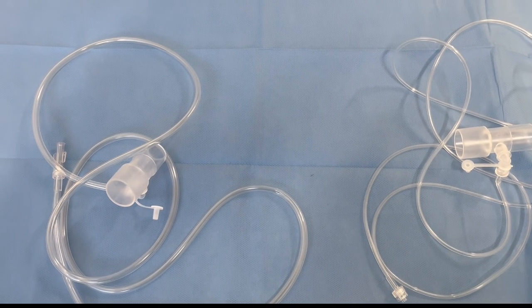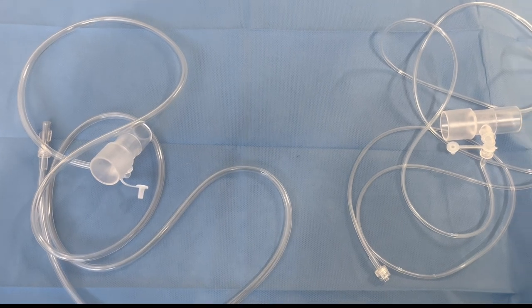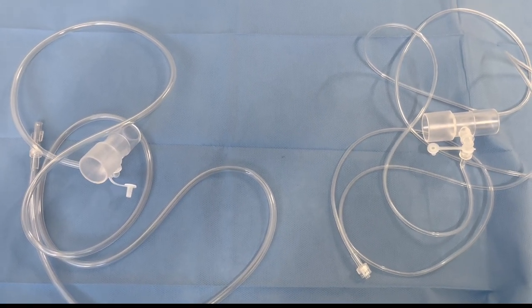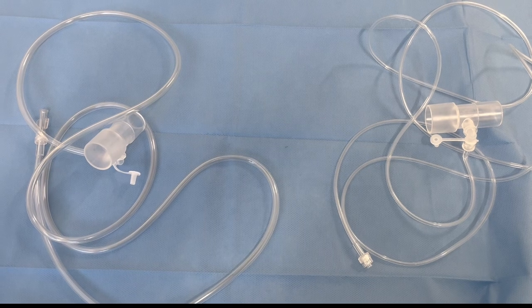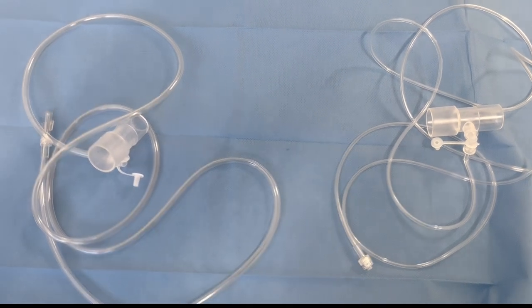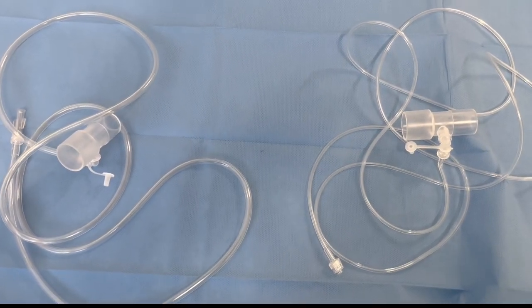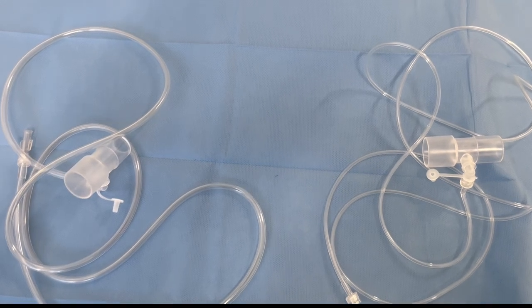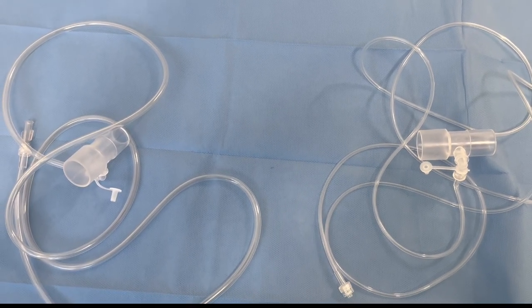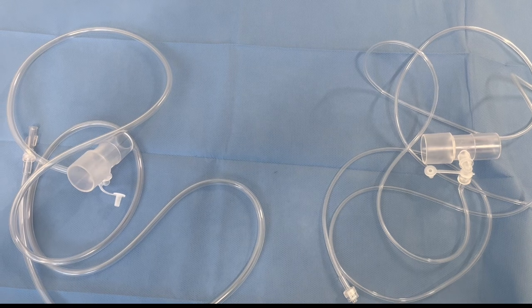Before we use the machine, we should familiarise ourselves with the disposables. One potential problem that has been identified early is the identical nature of the nitric injection adapter and the sample line adapter. This could lead to the sample line being connected onto the humidifier, potentially breaking the machine.